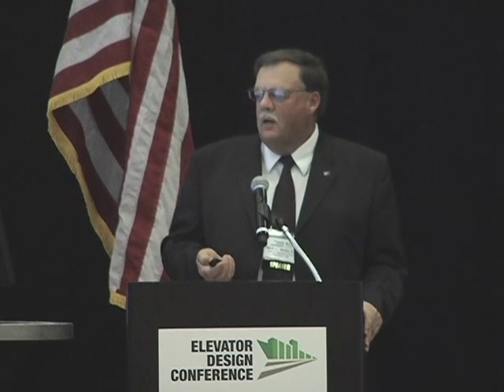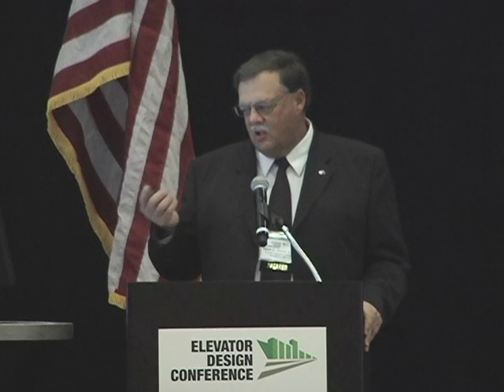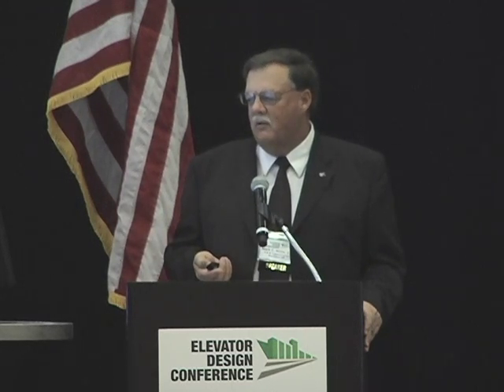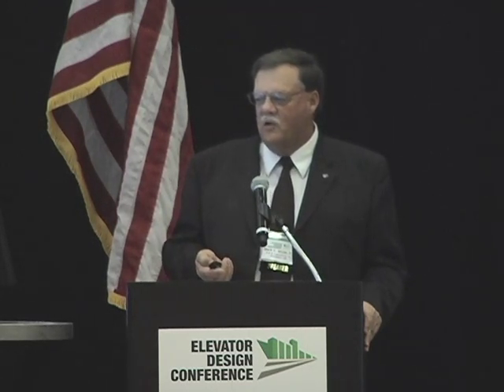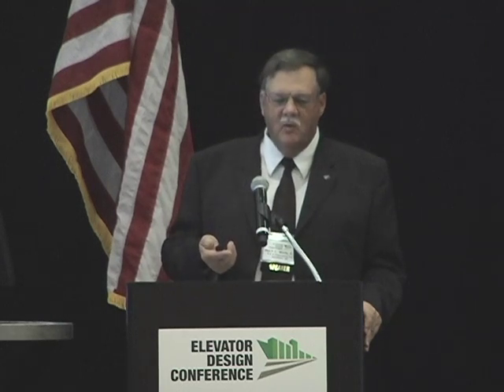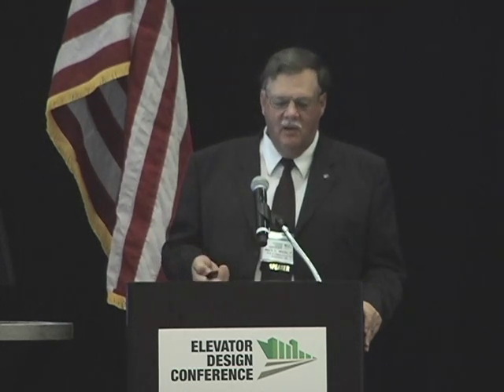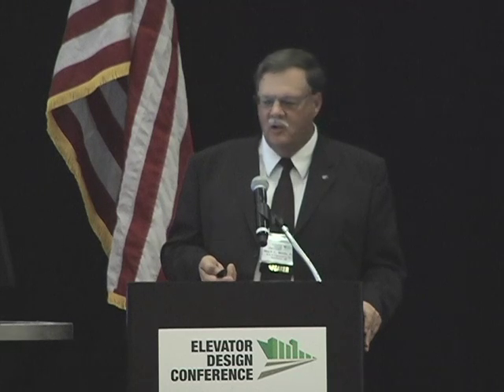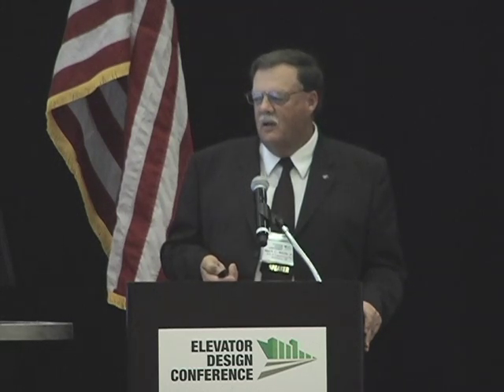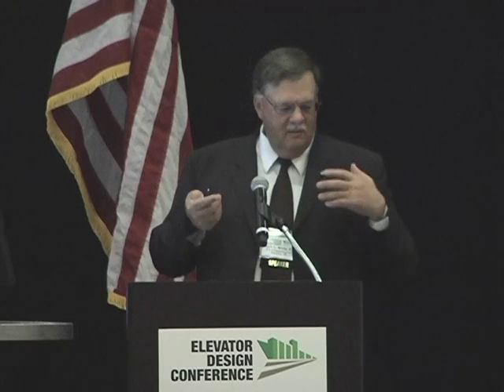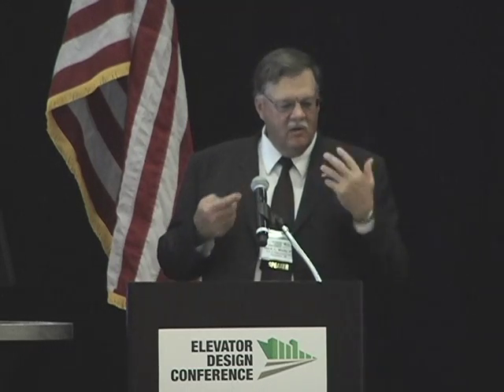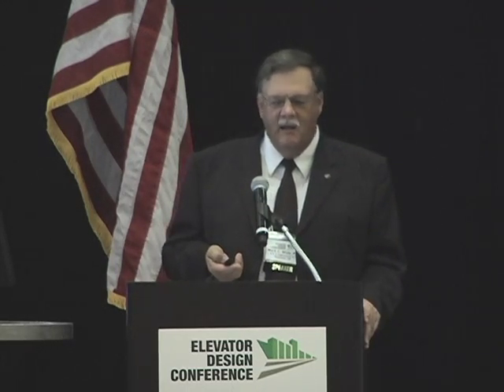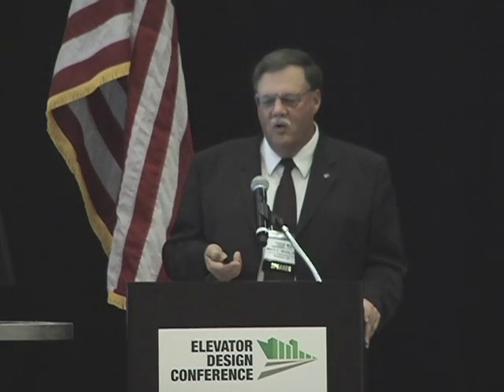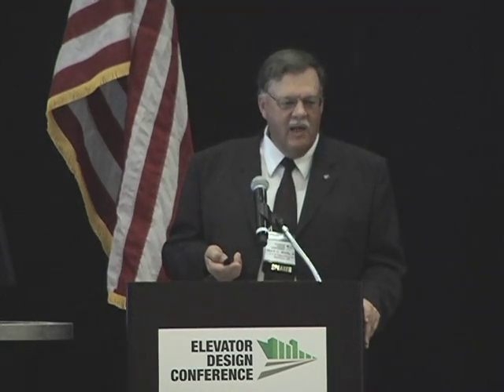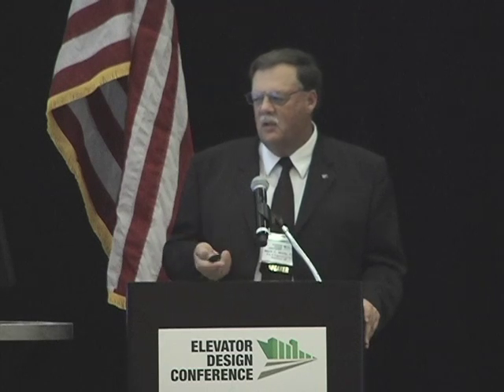So, and of course, classification principles, whether it's an enclosed area, the dust accumulation, which has been talked about in other discussions, whether it's present normally or abnormally. It gets into whether Division 1 means you think it's going to normally be present no matter what you can do at some periods of time. And Division 2 is you've got everything enclosed, good dust control, good housekeeping, and you say, well, it's going to be only if something goes wrong. If I get hazardous dust accumulation, then it becomes Division 2.